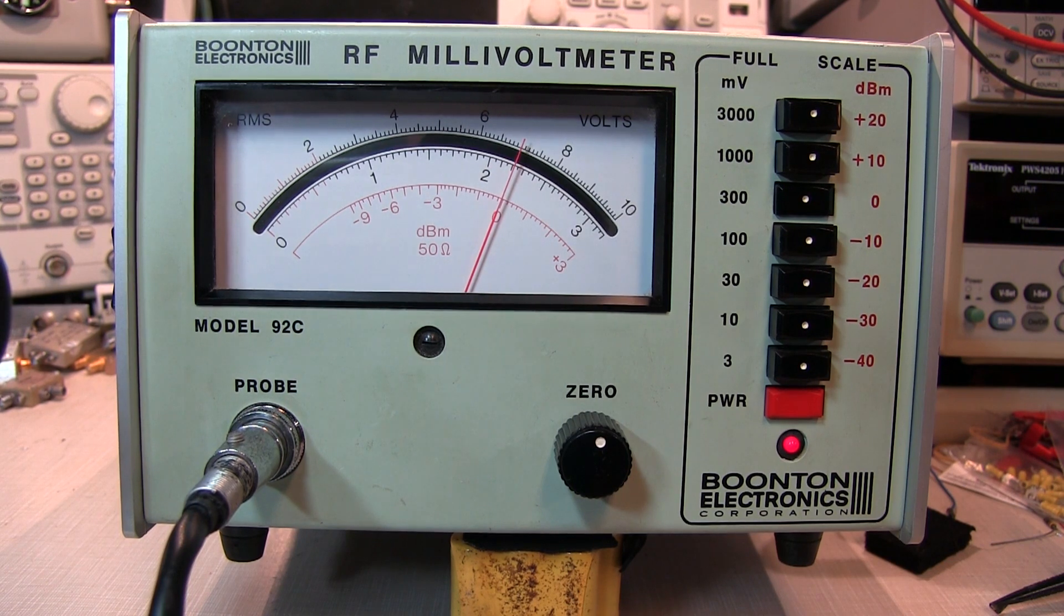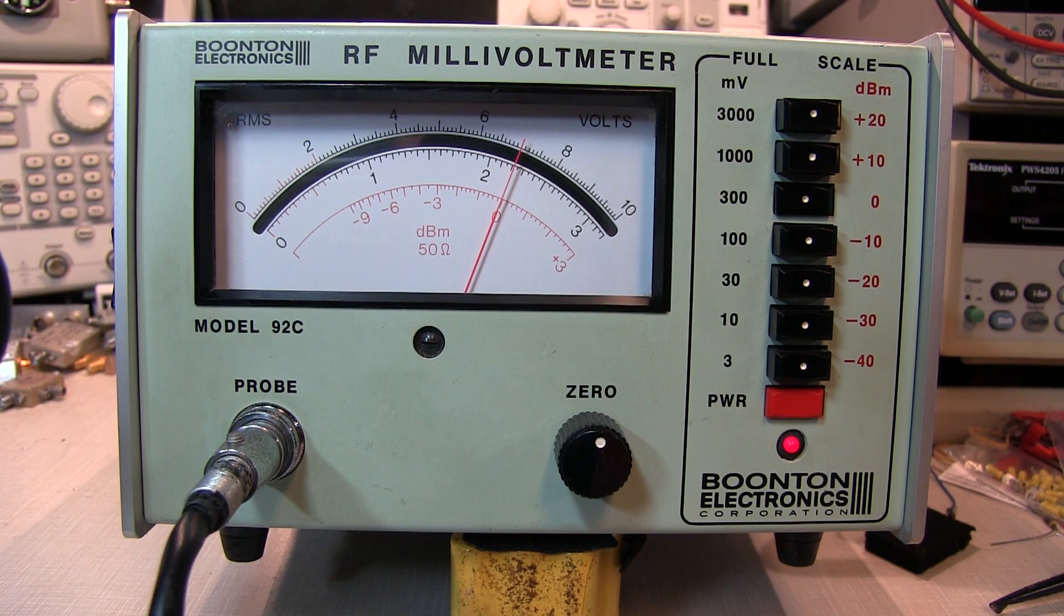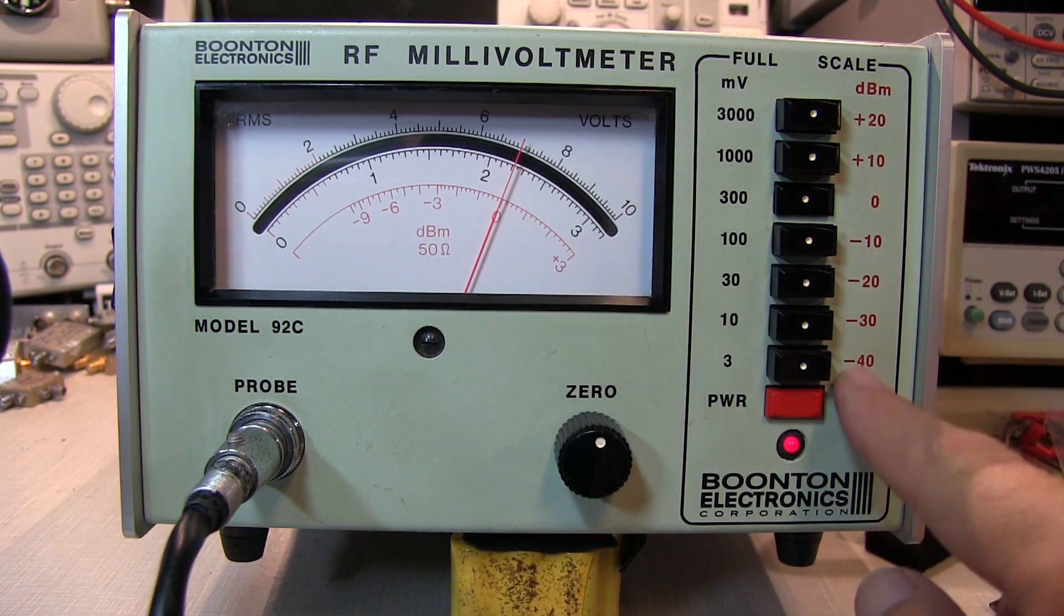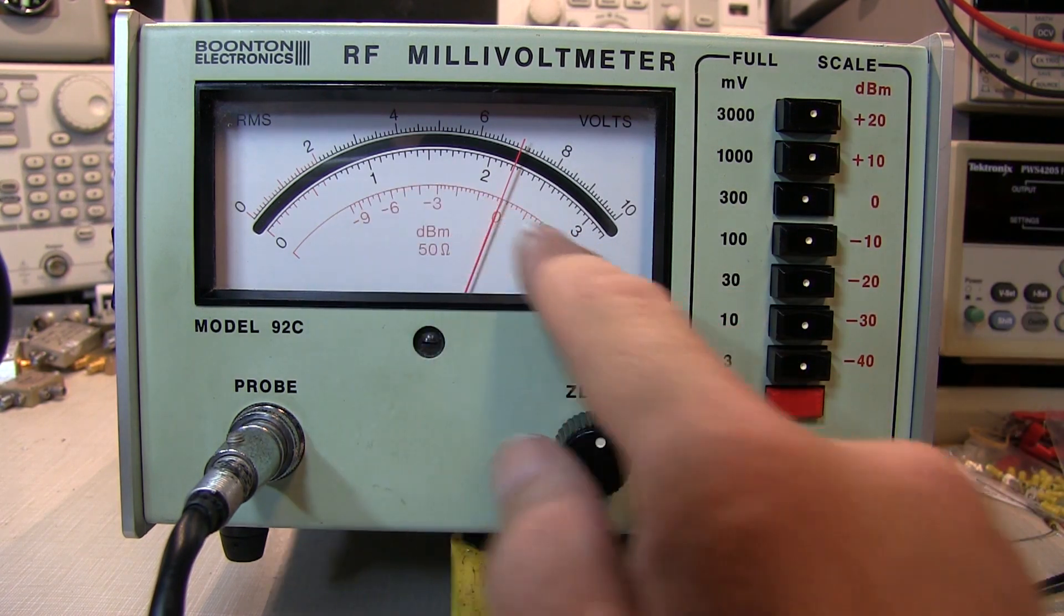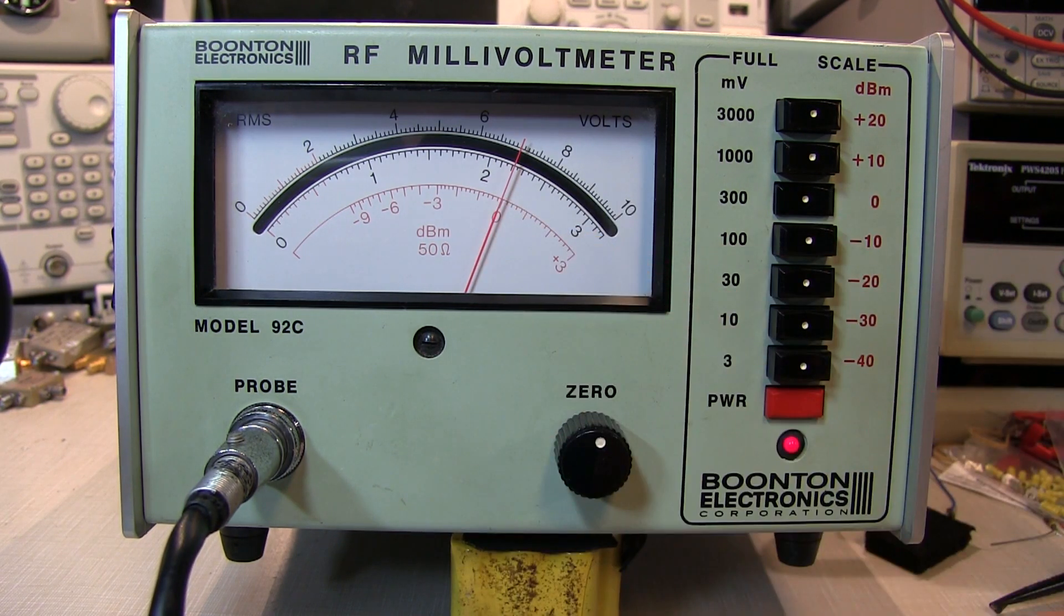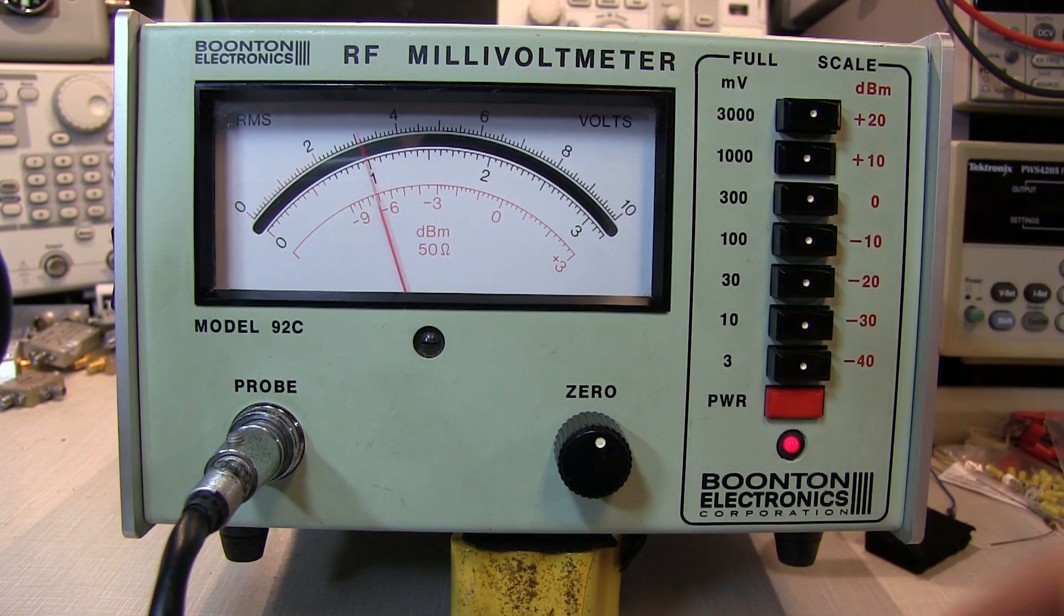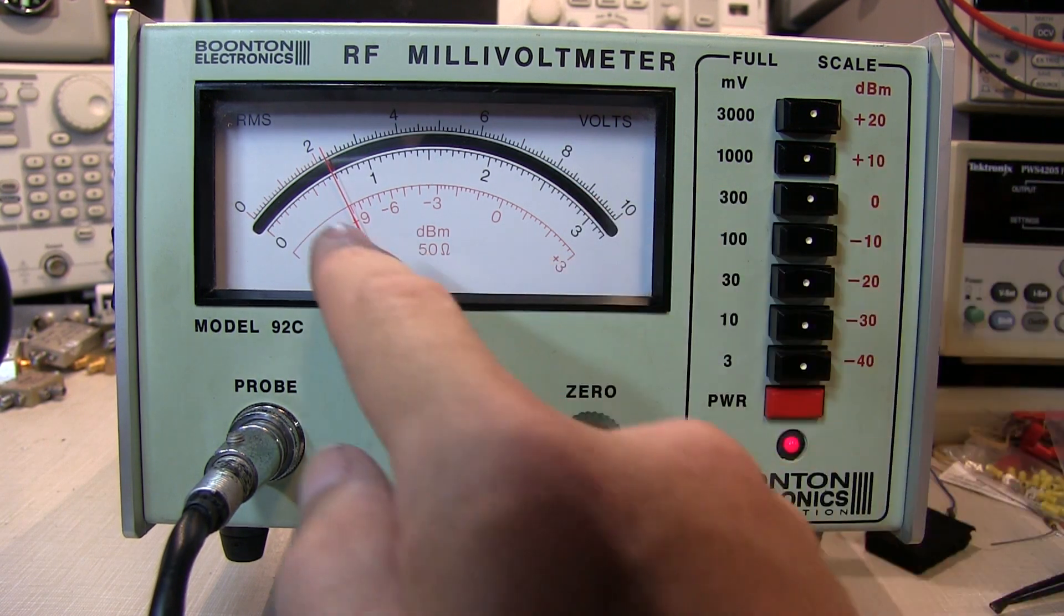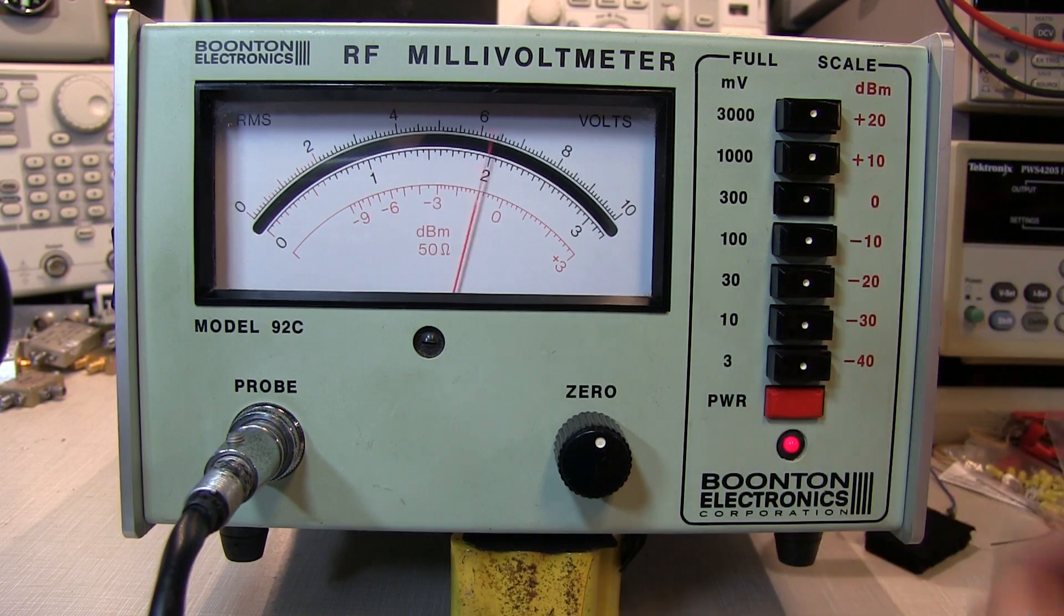And lo and behold, that reads right dead on top of 0 dBm. The way the dBm scale works on here is, depending on what scale you've got, you add or subtract the dBm reading from the setting. So in this case, when it's set to 0 and it reads 0, we have 0 dBm. You'll notice if I set this to plus 10 dBm, and the meter now is going to read down here at minus 10, so I'm going to have plus 10, minus 10, so that's still 0 dBm. So that's how the dBm scales work.